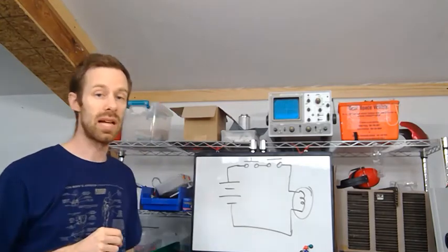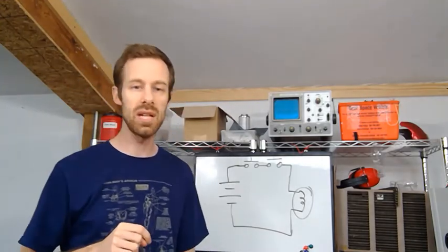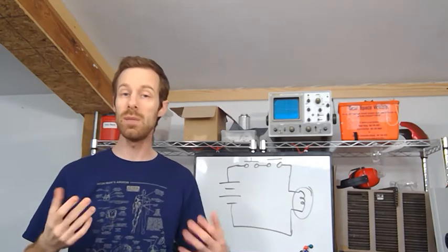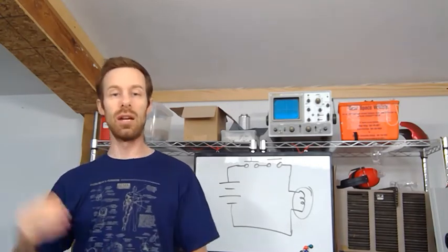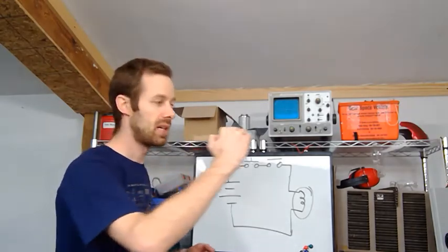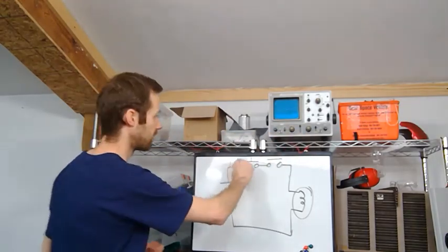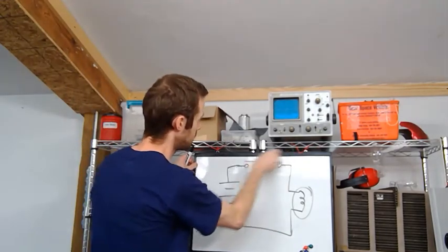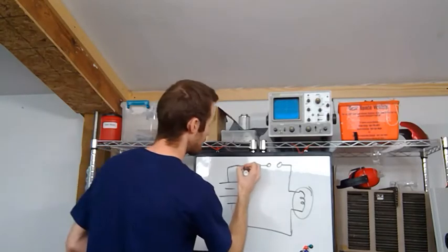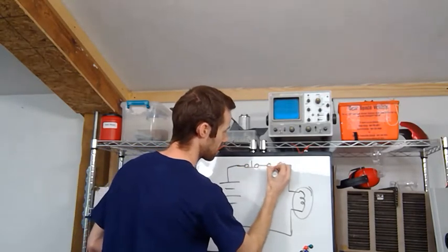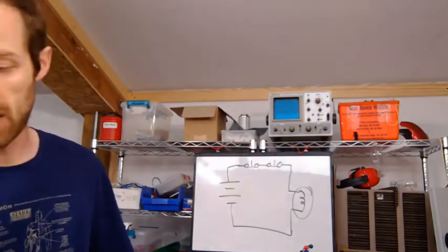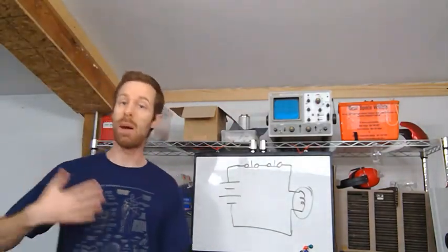Now, most of the time, you're likely to see normally closed series when we're dealing with emergency stop situations. If you have emergency stop buttons, they are all going to be normally closed in series with each other. So if these were normally closed, let me go ahead and redraw them as normally closed here. The switch symbol for that looks awfully similar, except the lines are underneath and touching the circles. Two normally closed switches. So as long as I don't press them, the light's going to be on. Or my machine is running.